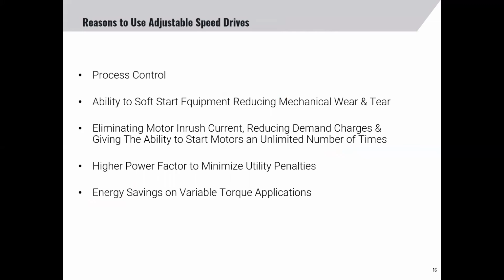So if I understand correctly, adding an adjustable speed drive to a system could actually reduce the overall system efficiency? So what are the reasons for using adjustable speed drives? Well, Mark, one of the first reasons is process control. When you use an adjustable speed drive with an electric motor, you now have the ability to speed up or slow down the motor, which offers you more precise motor control and speed control for your application.